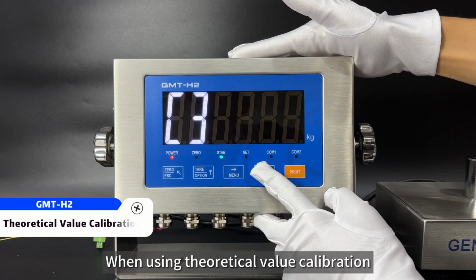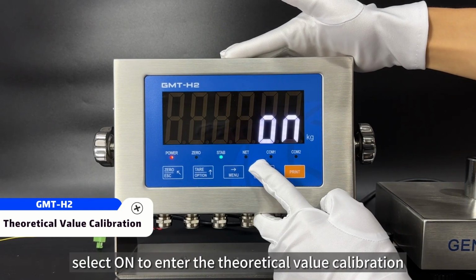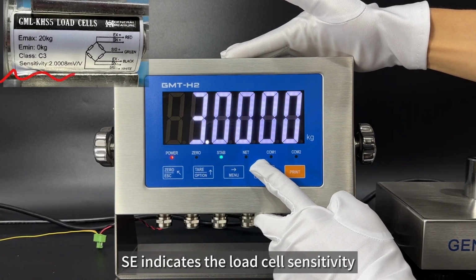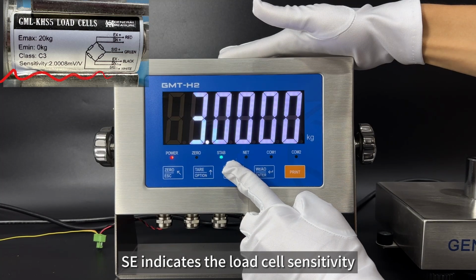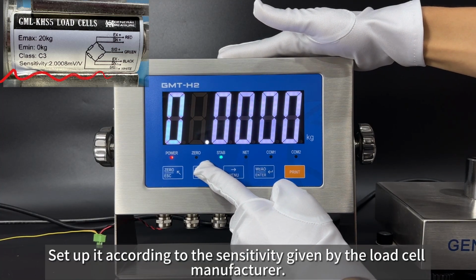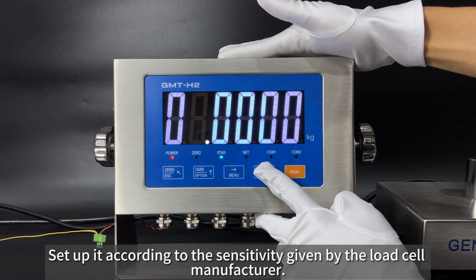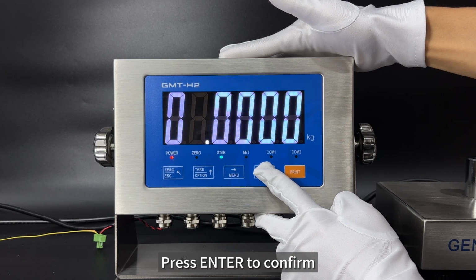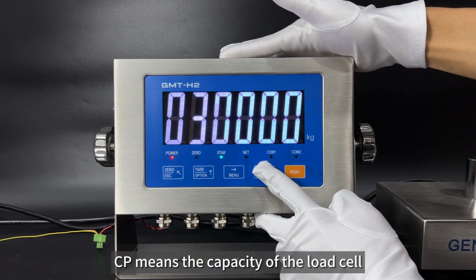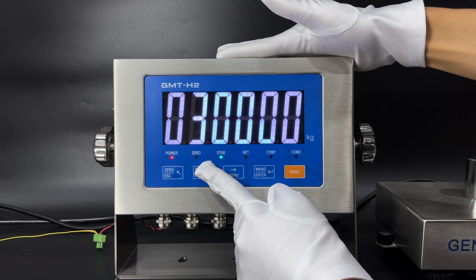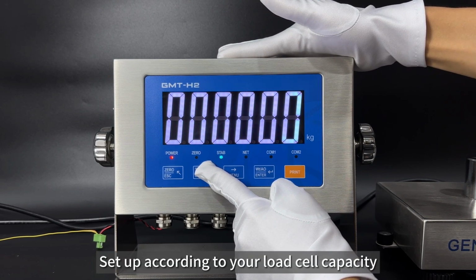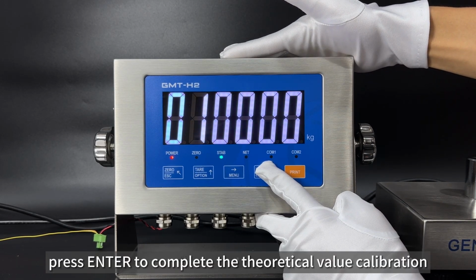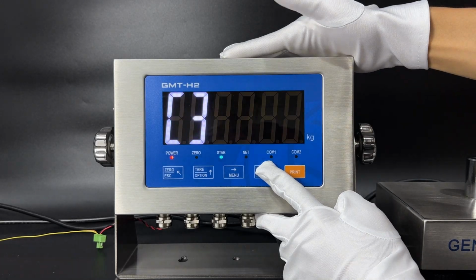When using theoretical value calibration, select on to enter the theoretical value calibration. SE indicates the load cell sensitivity. Set it up according to the sensitivity given by the load cell manufacturer. Press enter to confirm. CP means the capacity of the load cell. Set up according to your load cell capacity. Press enter to complete the theoretical value calibration.